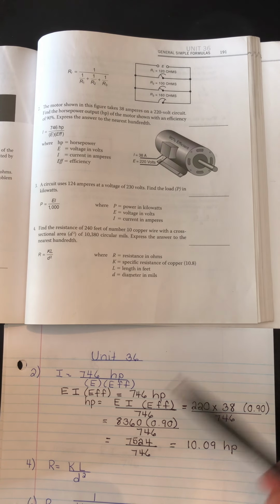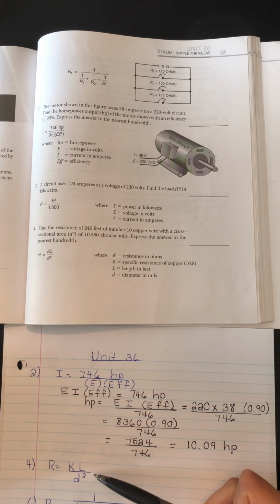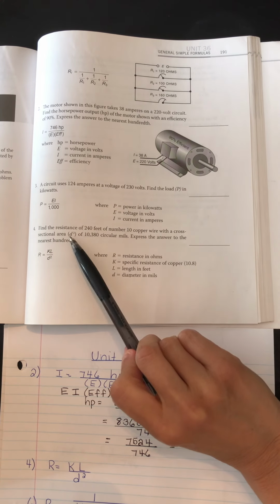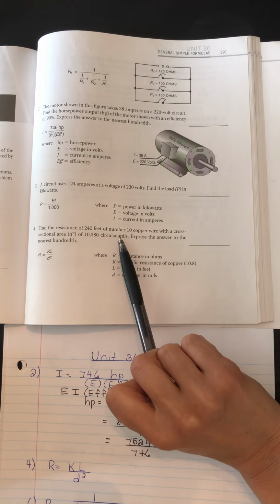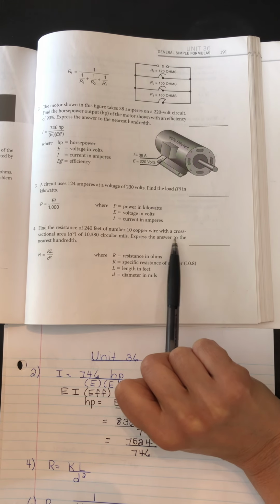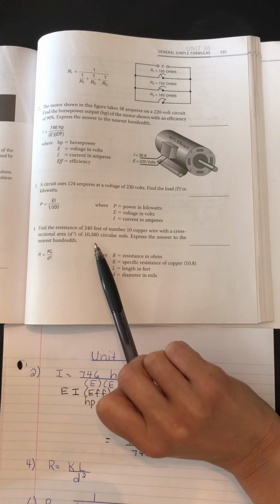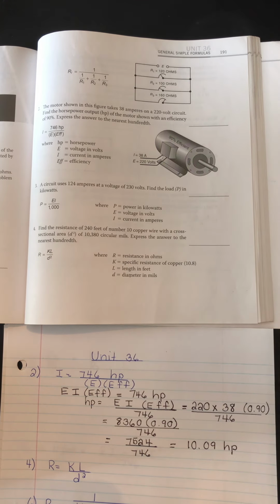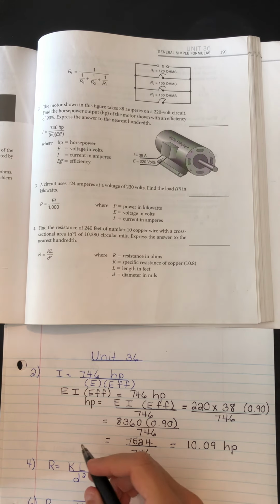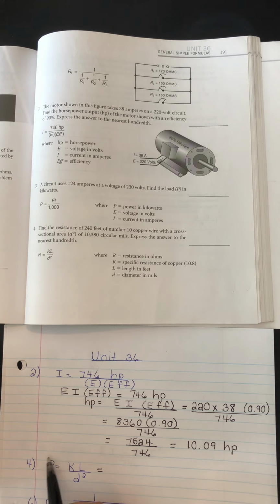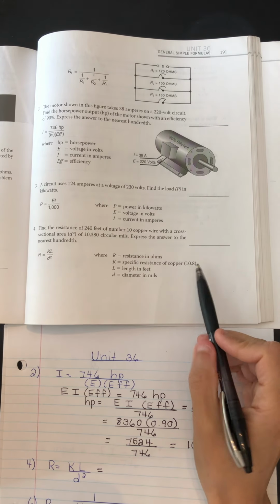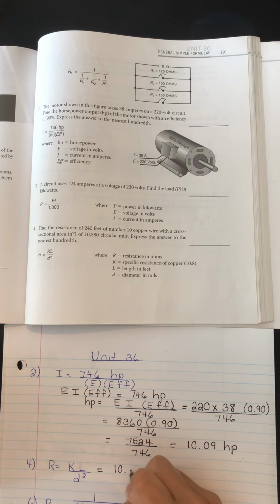Okay, let's go on to number four. Number four gives us this formula here. And it asks us to find the resistance. Find the resistance of 240 feet of number 10 copper wire with a cross-sectional area of 10,380 circular mils. Okay, so all we need to do is substitute because we're finding the resistance and it is already isolated. So K, and we saw this formula in a previous lesson, K, it reminds us, is the constant 10.8, which is specific to copper.